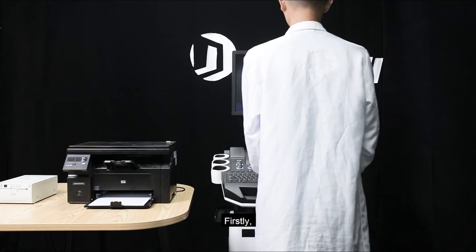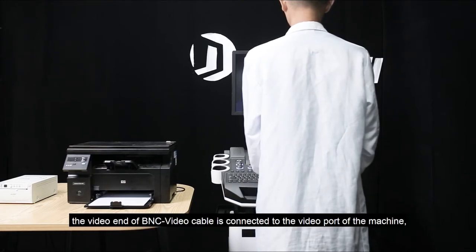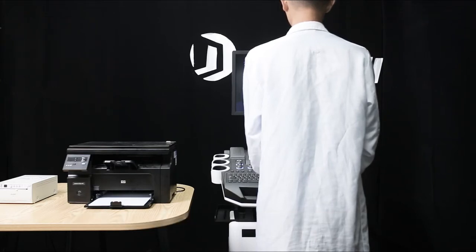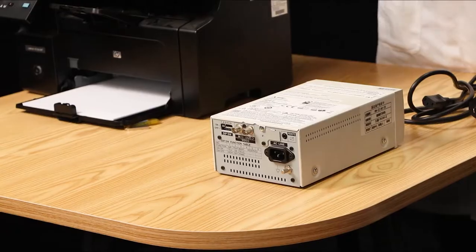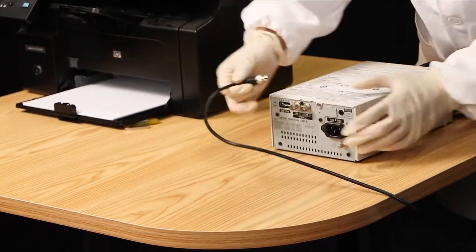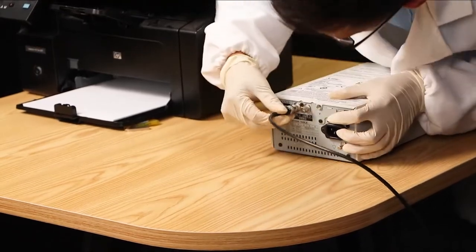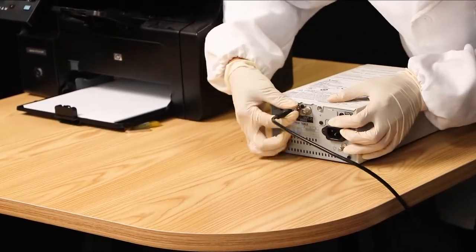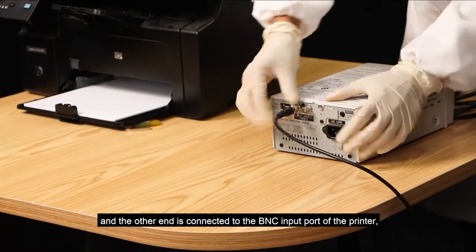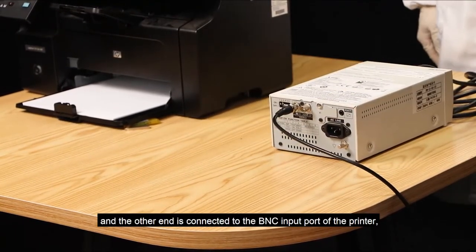Video printer. Firstly, the video end of the BNC to video cable is connected to the video port of the machine. And the other end is connected to the BNC input port of the printer.